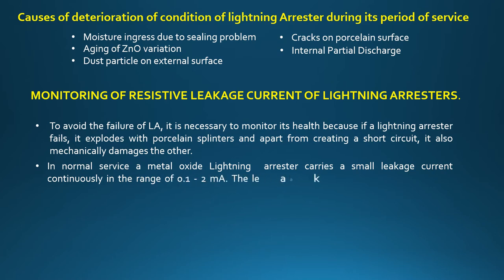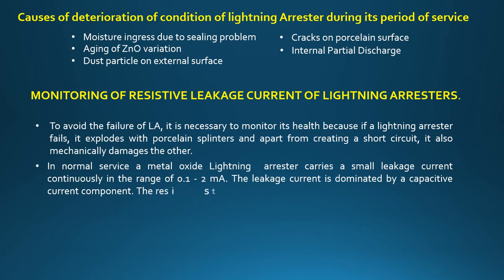In normal service, a metal oxide lightning arrester carries a small leakage current continuously in the range of 0.1 to 2 milliampere. The leakage current is dominated by a capacitive current component. The resistive component may be in the range of 5 to 25 percent of the capacitive component.